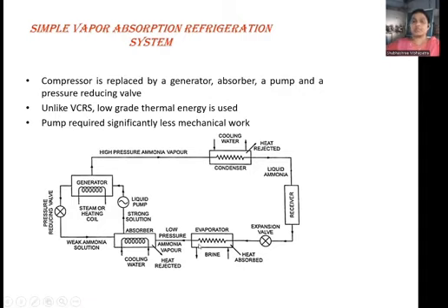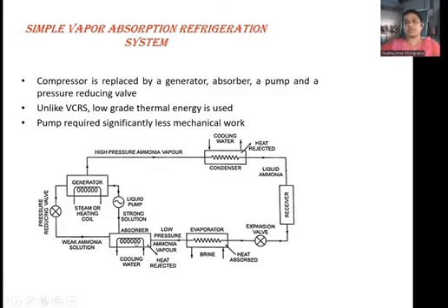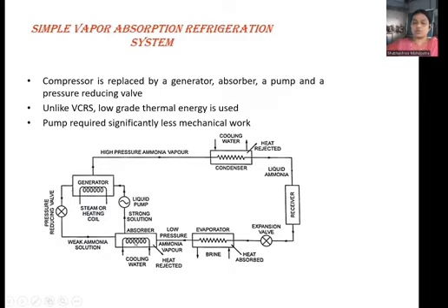This vapor refrigerant gets drawn by the absorber. Here the absorbent is present, which draws more and more ammonia, and a strong solution of aqua ammonia is created. As the water absorbs the ammonia, its pressure drops and more ammonia is drawn from the evaporator. Thus, a strong solution is prepared at the absorber. This strong aqua ammonia solution is then pumped by the liquid pump to the generator.